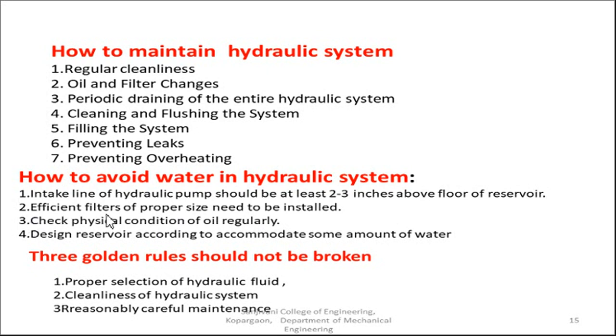Efficient filters of proper sizes need to be installed in the circuit depending on the application and the nature of contamination of the application zone. Then check the physical condition of the oil regularly. Then design the reservoir to accommodate the amount of water. That means you have to presume that some amount of water may get formed in the hydraulic system, and then design your system accordingly.